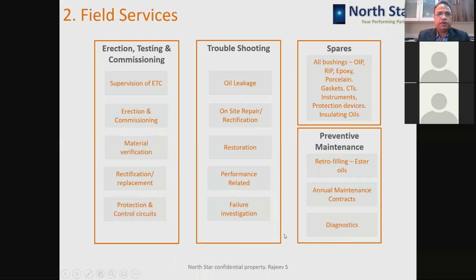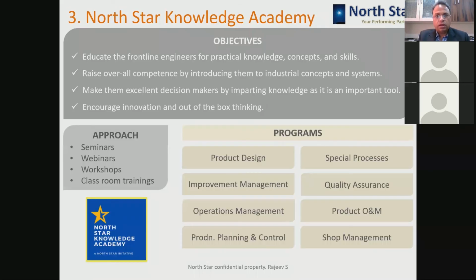Second area of our intervention is field services, where we have a dedicated team of experienced engineers and technicians, and we take up end-to-end site support, starting from erection, testing, commissioning to troubleshooting to annual maintenance contracts to diagnostics, providing spares, all kinds of spares like condenser bushings or epoxy bushings or CTs, instruments, insulating oils. We also support our customers in carrying out diagnostics, and that includes assessment of remaining life of the transformer. That comes very useful when we think about replacing the existing mineral oil with natural or synthetic esters.